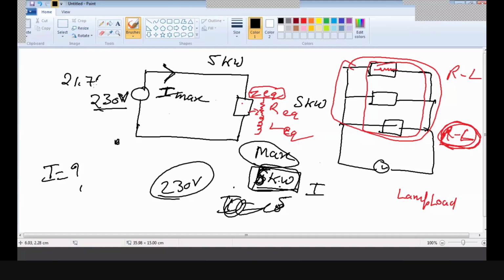21.7 ampere. If you are calculating this, suppose you get 21.7 ampere. So this is the maximum limit of current for your circuit. You cannot connect more than 5 kilowatt of load, because if you connect more than 5 kilowatt, your current will also increase, more than 21.7 ampere will flow in the circuit. That is not desirable. Every circuit has its own limit.